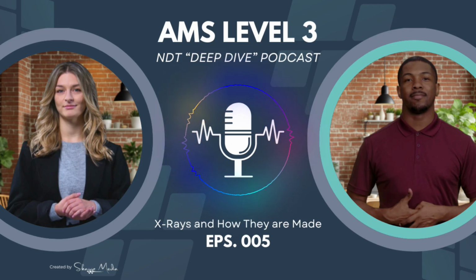So how do you focus that electron beam? Several ways. The most common is the focusing cup. The filament sits inside a small recess in the cathode structure. This cup is shaped to create an electric field that pushes the electrons together, repelling them from the sides, focusing them into a tight beam aimed at the anode target. Clever.